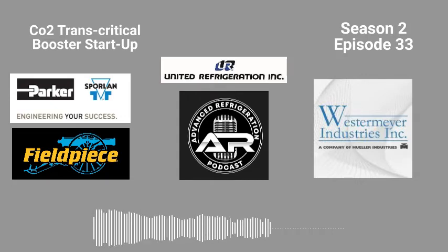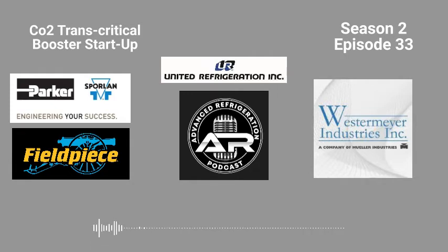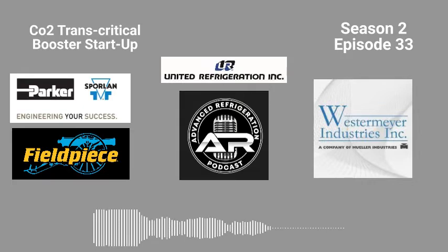Just go straight in the flash tank. I usually just use a black charging hose. So, black 3/8 charging hose, and I'll get it up to about 100, 125 pounds. And with vapor, just let it all kind of settle out and go out through the cases. And I forgot, you have to put oil in the rack. Wait, really? None of them come with it? Yeah, you have to put oil in the rack.